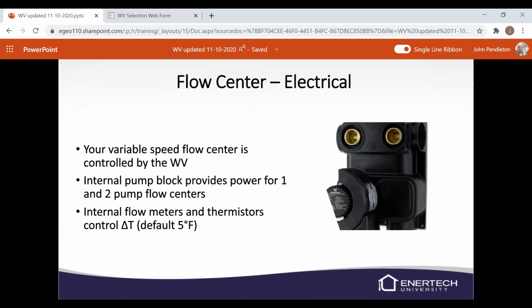Flow center. The variable speed flow center for your source and the load are controlled by the WV controllers. So there is an internal pump block that provides power for 1 or 2 pump flow centers, and there is an internal flow meter and thermistors that control delta T, or temperature difference. So it tries to maintain 5 degrees. It does have a little bit of a buffer on that, so if it can't respond quick enough, it's not going to immediately lock out if you get the 4 degree temperature difference. It's got a little bit of a buffer there.